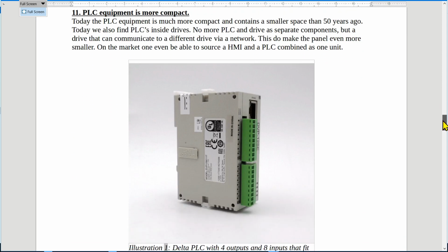Now, PLC equipment is much more compact. Today, the PLC equipment is much more compact and occupies a smaller space than 50 years ago. Today, we will also find PLCs inside drives, AC drives. It is no longer needed for a PLC and a drive to be separate components, but a drive that can communicate to a different drive via a network. Even temperature thermocouples can be interfaced directly to the drive without even purchasing a different PLC to fulfill their duties.